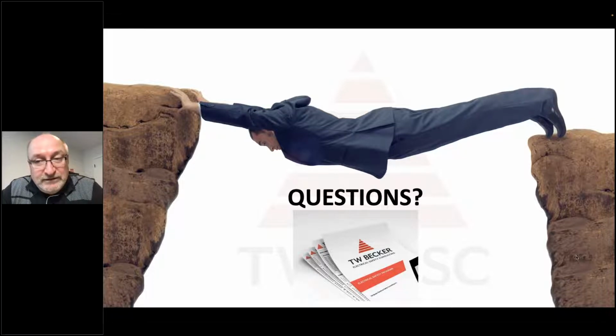So 70E, their tech committee didn't have time to review that. And in the 2024 edition of 70E, they did not review it and did not update and include an arc flash PPE category 5 in the arc flash PPE category method in 70E. So it is a significant technical divergence, in my opinion.